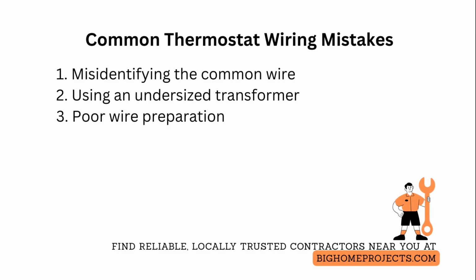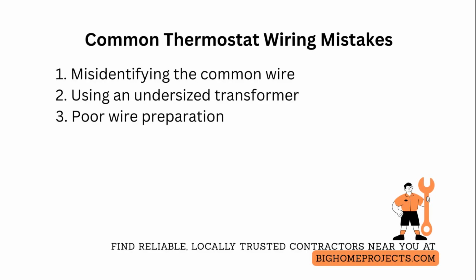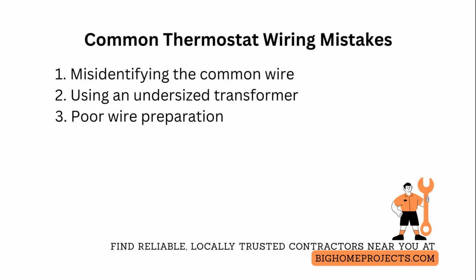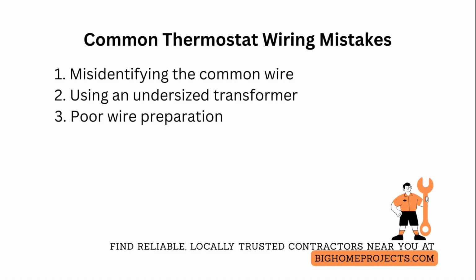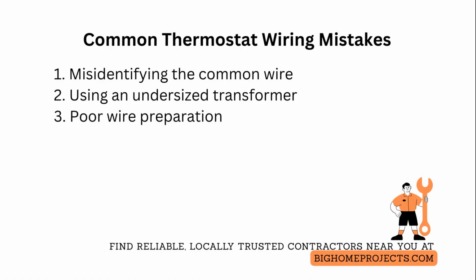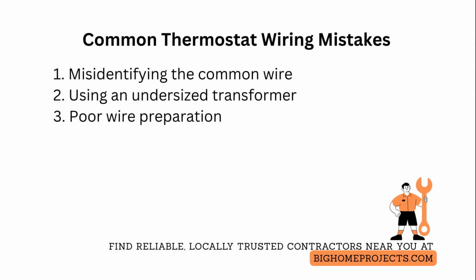One of the frequent installation errors is using an undersized transformer or an overloaded transformer from added accessories, causing low 24-volt AC and intermittent thermostat behavior. Correct this by measuring no-load and loaded voltage, and replacing the transformer with one rated for the thermostat plus accessories, or install a separate 24-volt transformer.